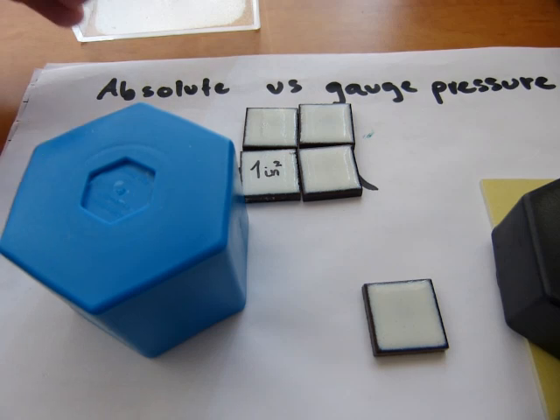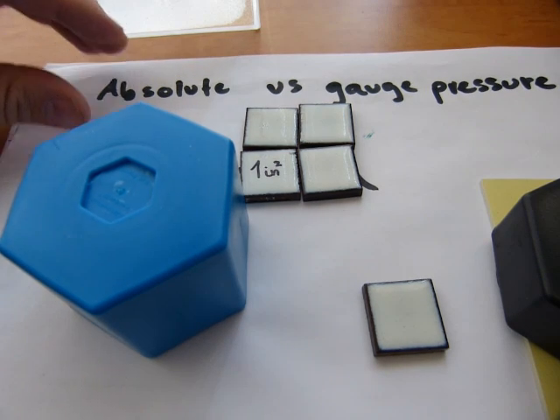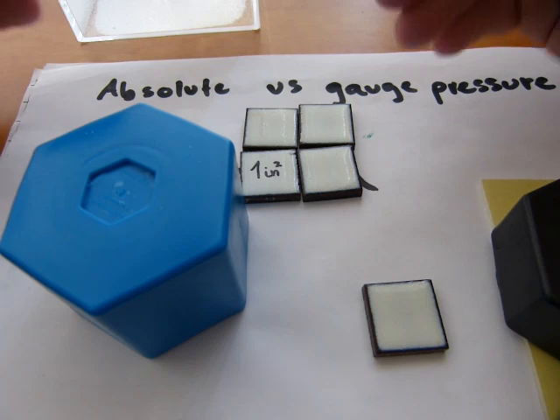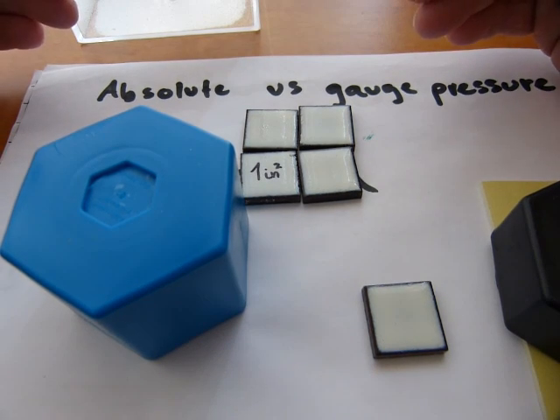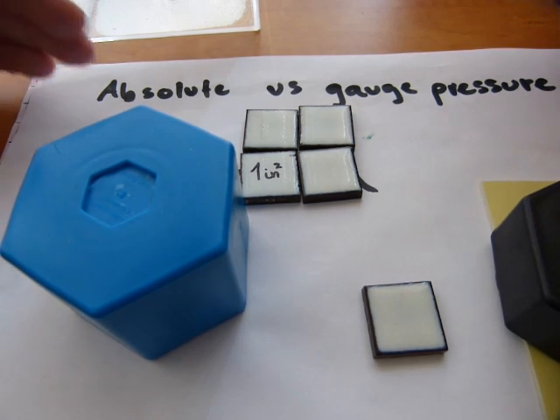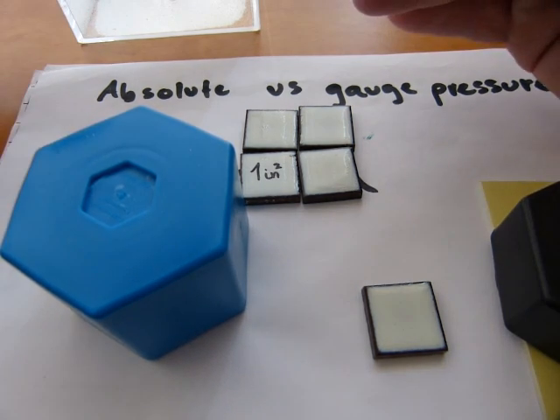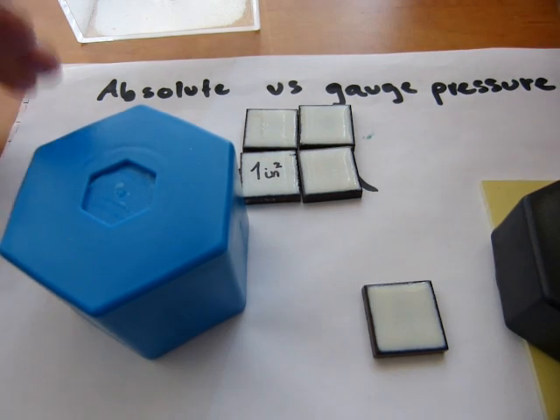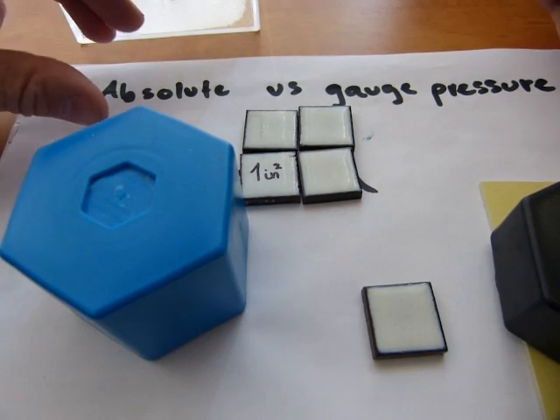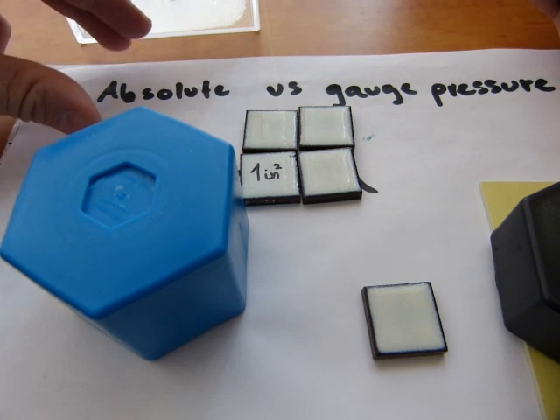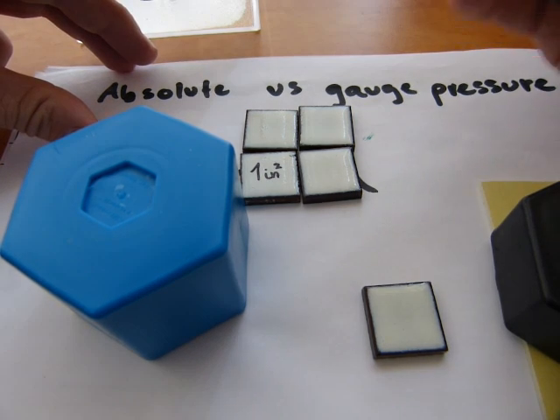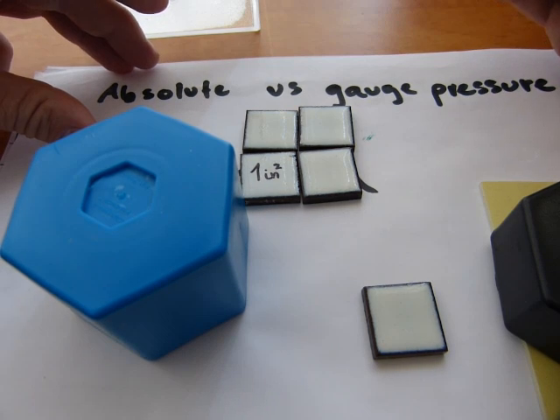So what's the difference? In either case, a pressure measurement is a comparative measurement. A comparison is made between inside or outside, or pressure being measured versus a reference. So in absolute measurement, the instrument is comparing a pressure to be measured against vacuum, where there's absolutely no pressure of any kind. So that's how absolute measurements are done.